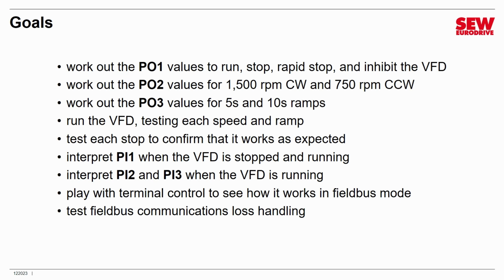In field bus mode, it does operate, but in a more limited way. And finally, as a bonus, we're going to test how the VFD handles communications loss during field bus operation. I'm just going to unplug the Ethernet cable and see if the VFD shuts down as we've set it up to do. So that's what I'm going to do. It's a lot of things to demonstrate, so again, keep your seatbelt fastened.